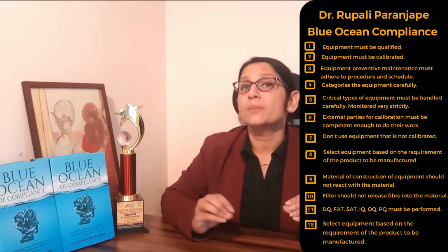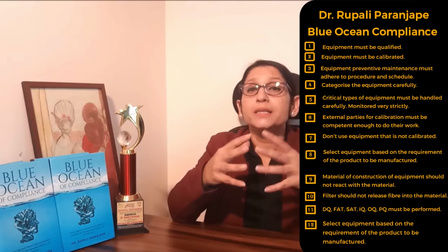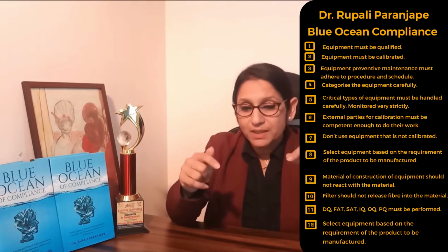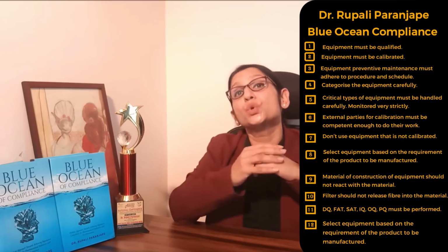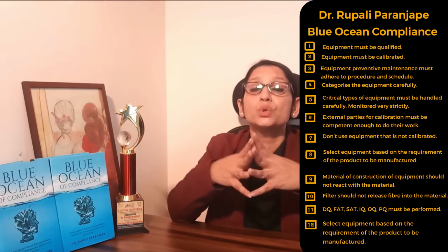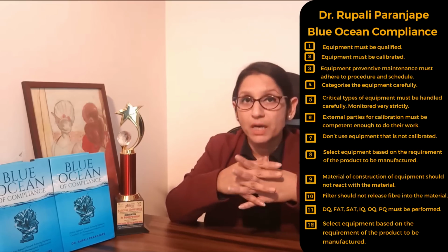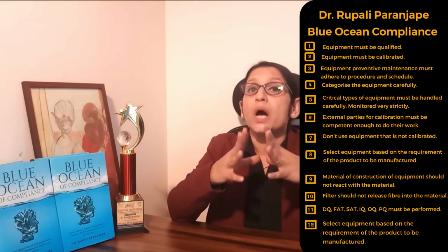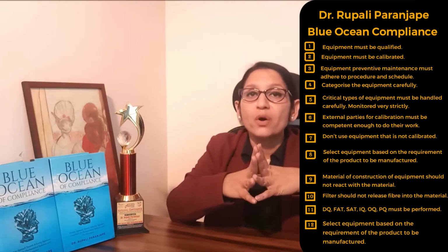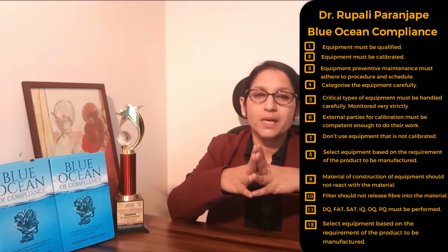These were a few compliance tips which should be followed while you are handling the equipment. The first thing is that whenever you receive any new equipment, or purchase any new equipment on your side, you will also have to ensure that DQ, IQ, OQ, PQ are performed, and FAT and SAT are performed, right?